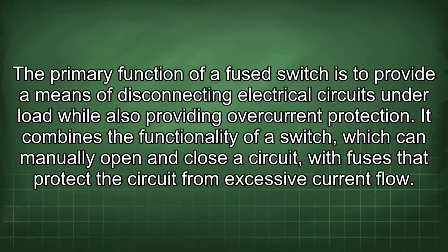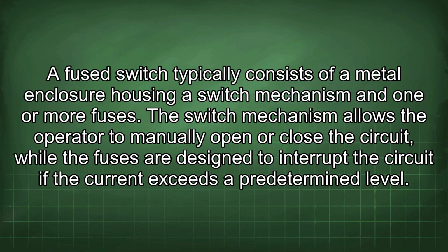The primary function of a fuse switch is to provide a means of disconnecting electrical circuits under load while also providing overcurrent protection. It combines the functionality of a switch, which can manually open and close a circuit, with fuses that protect the circuit from excessive current flow. A fuse switch typically consists of a metal enclosure housing a switch mechanism and one or more fuses. The switch mechanism allows the operator to manually open or close the circuit, while the fuses are designed to interrupt the circuit if the current exceeds a predetermined level.